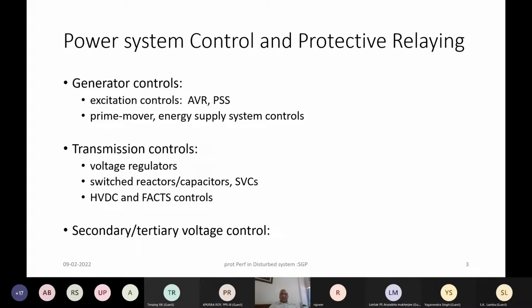Protection as well as controls. We have seen that basically on the generation power station side, it's the AVR, the governor, and power system stabilizers. These are the primary generator controls. On the transmission side, again, for voltage control, by way of reactors, capacitors, SVCs, HVDC lines, FACTS control. These are the control mechanisms on the transmission side. And then secondary and tertiary control for the purpose of managing the frequency and the loading on various circuits.